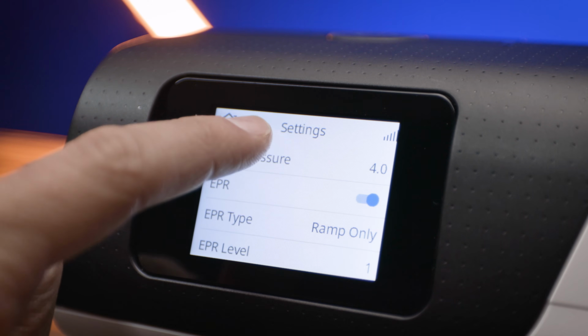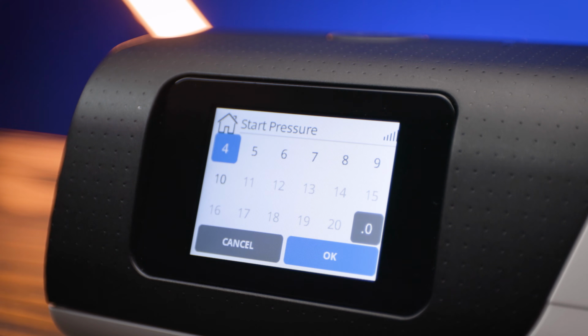When it comes to setting up ramp, there are two things to decide. First, you need to set a starting pressure. This is the pressure level the device will provide when it is turned on. If you think about the ramp analogy, this is the level of pressure at the bottom of the ramp. It will go up from here.